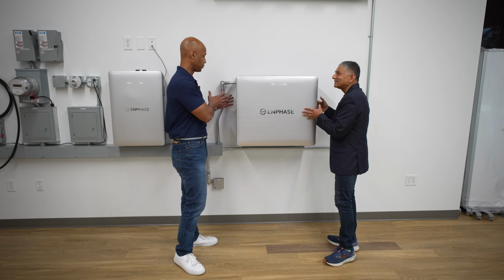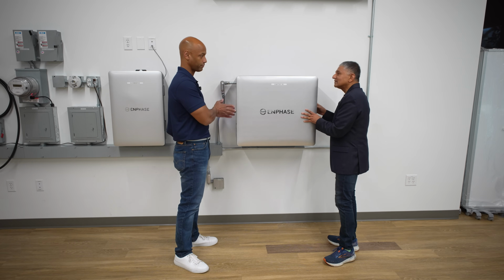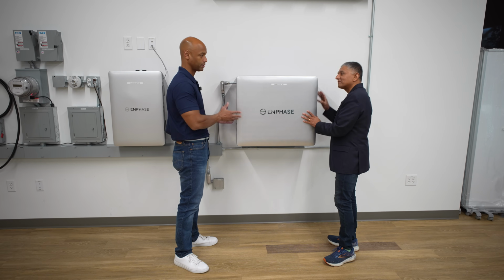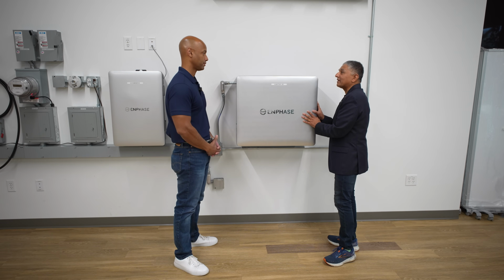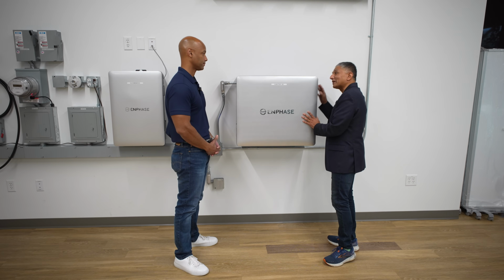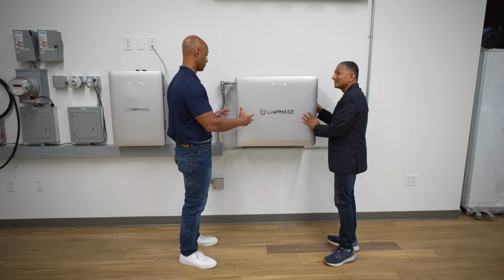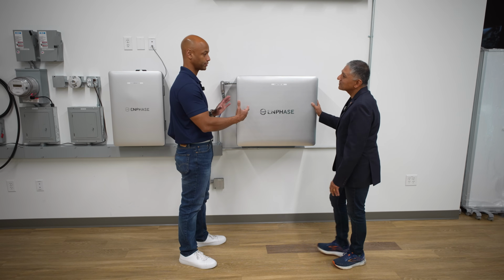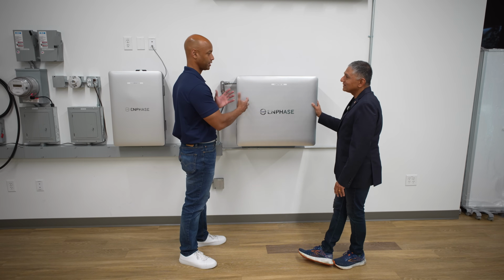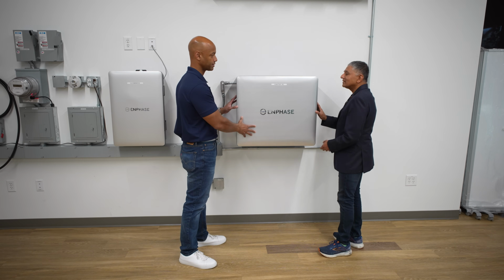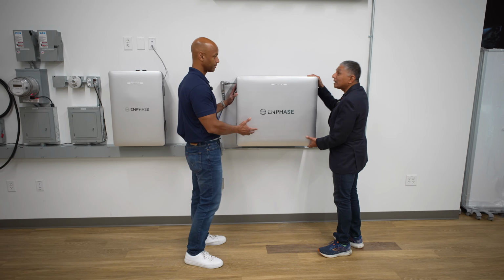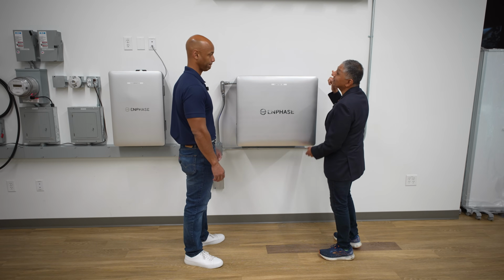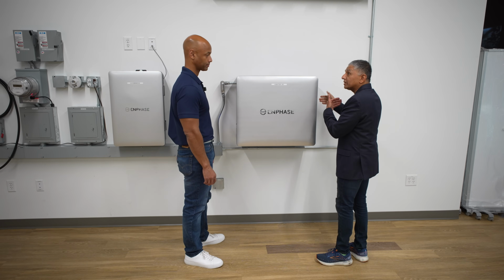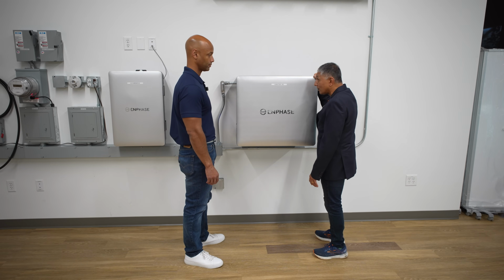So are they two parallel 5 kilowatt hour units, where if one fails you still get half the capacity? Precisely, in fact there are 2 inverters in here, so if one were to fail, you still get the other to continue operating. So you're still using microinverters internally for that charging. Are they arranged differently to get tighter energy density? It does seem like a much more dense battery. It's 62% less wall space, of course it's deeper, but that's a huge advantage as well.